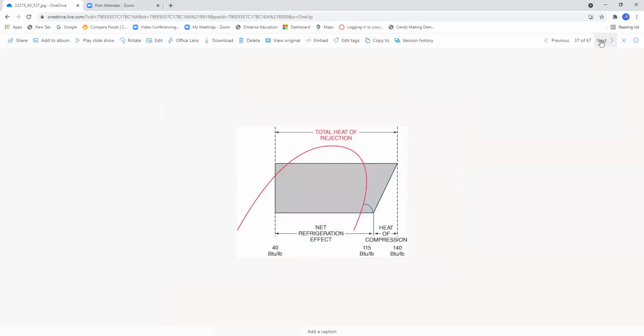Okay, this is the total heat of rejection, the net refrigeration effect, and the heat of compression on a heat pump. And heat pumps, in their very nature, are a very efficient machine when they're designed properly, installed properly, and charged properly. That being said, if you take some shortcuts and don't do the job right, you are going to have problems with this system.